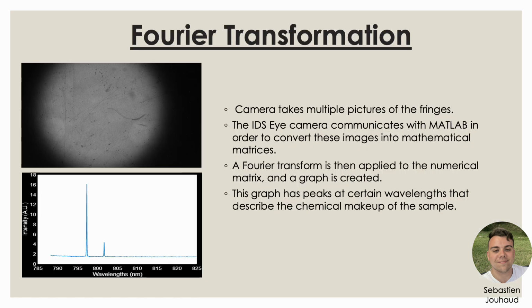Fourier transformations are actually vital to being able to generate the waveform that means something, the spectrometer results. What happens when you run the laser is that a camera takes pictures of the light that comes out through the sample. This camera is called the IDS Eye, and it is what actually converts these images into mathematical matrices. You can see an example of one of those images on the top left. They don't look like much, but after a series of conversions and calculations and eventually a Fourier transform, the numerical matrices are transformed into a graph. The graph is what you see at the bottom left, and it has peaks at certain wavelengths. Each of these wavelengths corresponds to a specific chemical makeup, or chemical signature, and these combined signatures will tell you what exactly is present in the sample being analyzed.